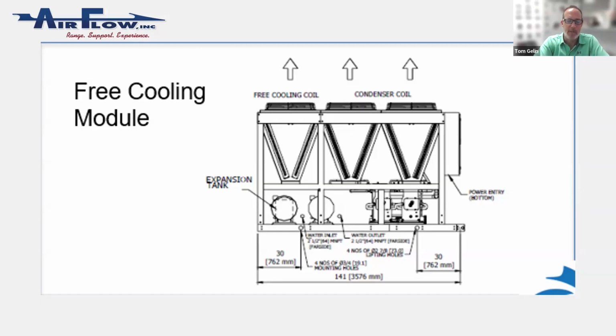I guess, yeah, not really a bypass. You would run the chilled water through the free cooling section of the module. So if it's cold outside, if it's below your chilled water temperature, so it's in the 30s and below, you just run your evaporator water, which is your chilled water supply. I'm not sure if you probably run your return, right? Because that's warmer. Through the free cooling coil and back into the evaporator. And then you're either running your compressor less or running it off.